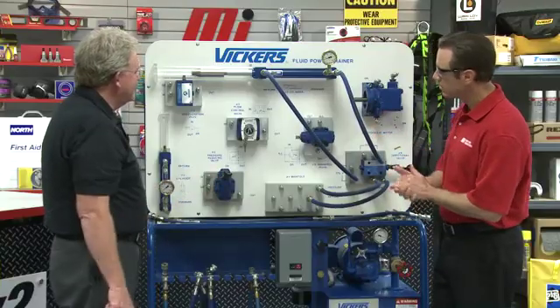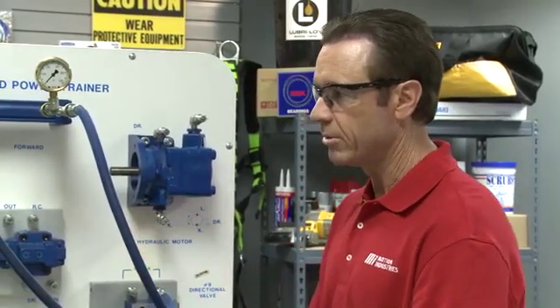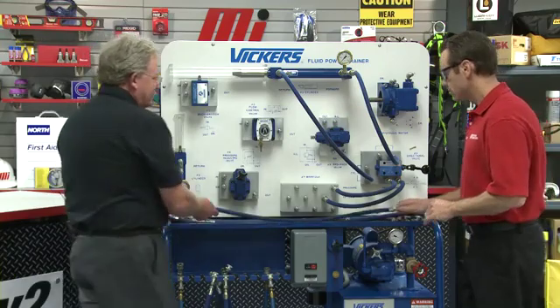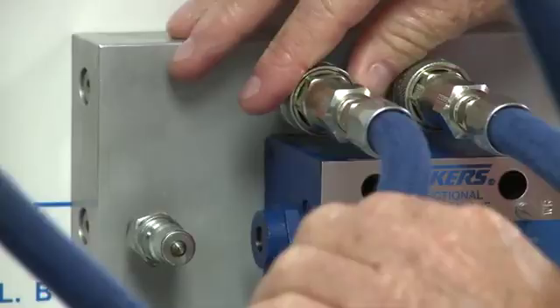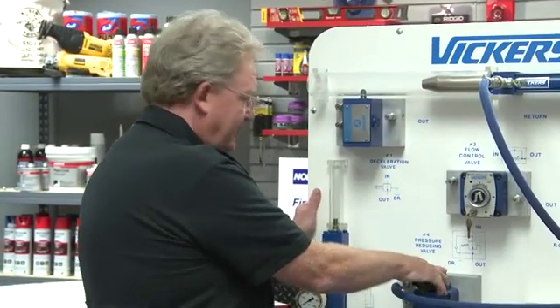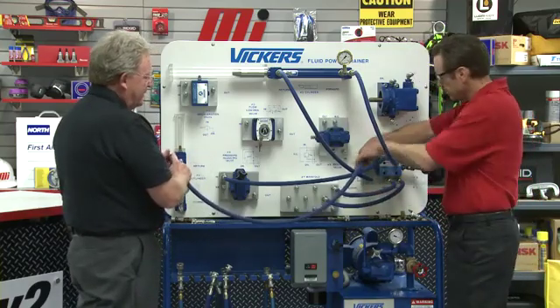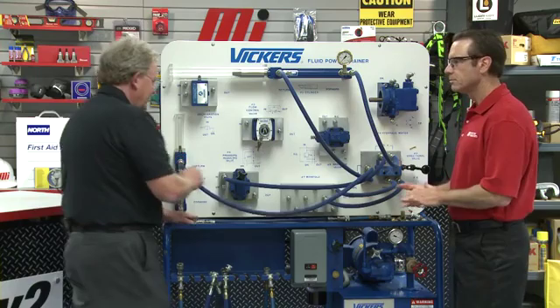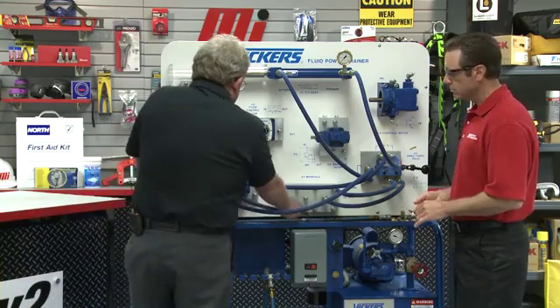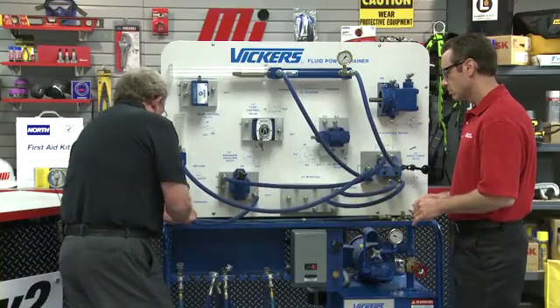Retract the cylinder, then I'll turn the unit off. Now we've got a few more hoses to connect. To start with, hook your end to the A port on the directional valve, and I will go to the IN port of the pressure-reducing valve. Next hose goes to the B port of the directional control valve, and my end will go to the rod end of the cylinder. Then there's a short one — from the out port of the pressure-reducing valve to the blind end of the cylinder.